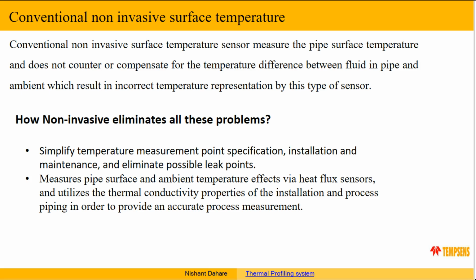So how does this non-invasive clamp sensor eliminate these problems compared to the conventional sensors? First, it simplifies temperature measurement - you don't need to drill, you don't need downtime, it's just plug and play. You just put the sensor below the pipe and measure the temperature. It also eliminates possible leak points.